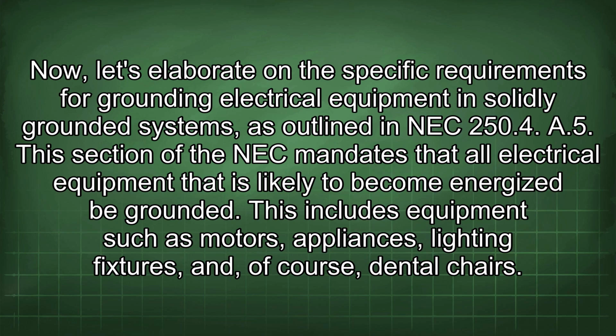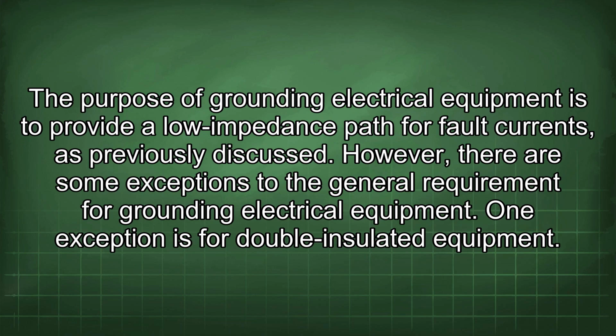Now let's elaborate on the specific requirements for grounding electrical equipment in solidly grounded systems, as outlined in NEC 250.4(A)(5). This section of the NEC mandates that all electrical equipment that is likely to become energized be grounded. This includes equipment such as motors, appliances, lighting fixtures, and, of course, dental chairs. The purpose of grounding electrical equipment is to provide a low impedance path for fault currents, as previously discussed. However, there are some exceptions to the general requirement for grounding electrical equipment.